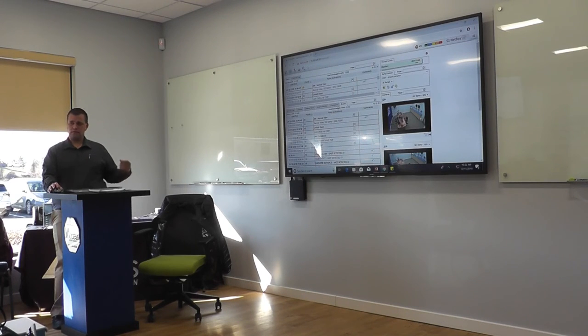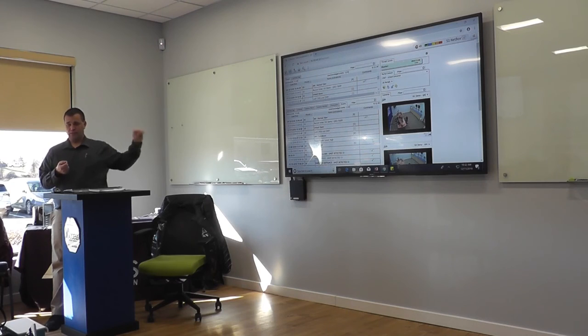and you can see after I clicked acknowledge, it went away. Some events, depending on what triggered them, will go away if that trigger has already been deactivated, if that makes sense. So for instance, if you had an event set up for a door held open and the door has shut, the event will stay on there until somebody goes and acknowledges it. Once you click acknowledge, it will go away. If that door is still held open though, it's still going to stay on there. It will be acknowledged, but it will stay on there until somebody actually closes the door. So again, these are configurable based on your needs. They would configure the events to display there if you needed them or acknowledged.